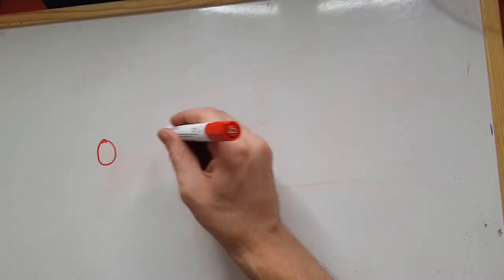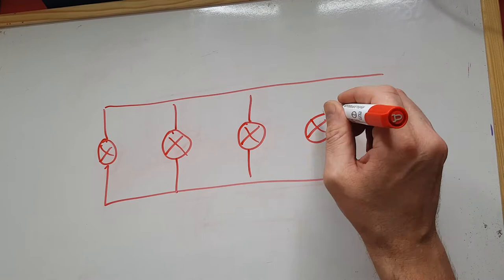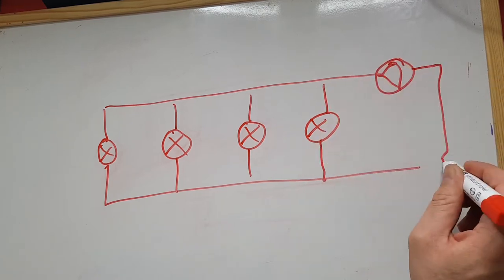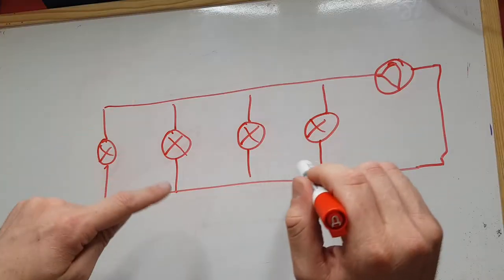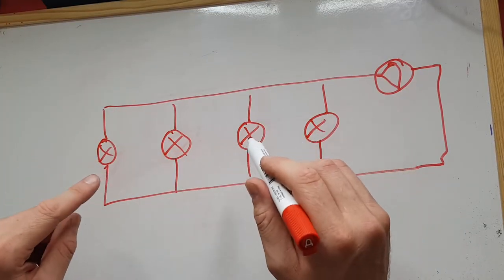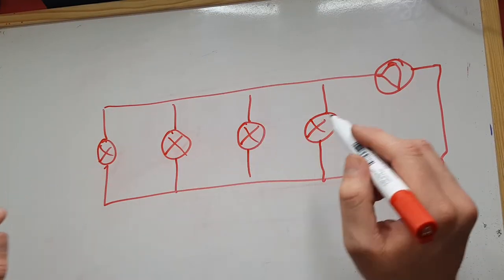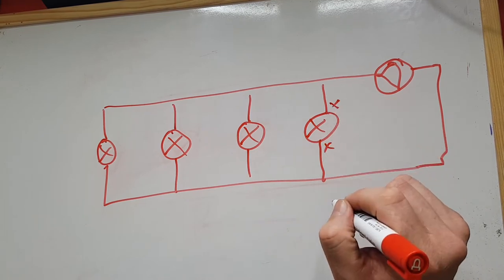So what do we mean by pressure independent control valves? Let's say we've got four valves on the same circuit. You can set these valves to allow a set flow rate through, and these valves will only allow that set flow rate through, regardless of the pressure either side of the valve.